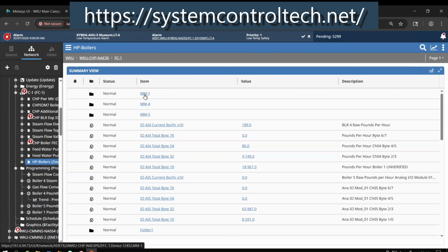And again, that's where we are going to do some data spanning. And this is where it gets kind of crazy. Remember, what we have is that initial span of that analog input signal from that sensor, from that power meter, or from that steam meter that's putting out an analog signal that is then being read by the controller. And that controller translates it and spans from 0 to 4,000. If you were to look at the panel on this, you're going to see on the panel there's a little note that says multiply by 10 to get the actual value, which we'll get into in a bit.